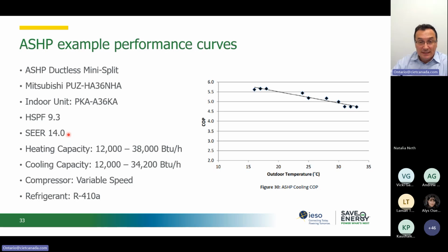So I just mentioned that in the summer we see less delta T. That's reflected in these two parameters. Capacity-wise, we also impact a bit the capacity of the heat exchanger with the temperatures. We can also take advantage in the heating mode of the heat of compression. So the electricity that we put in the compressor is now useful. So for that reason, sometimes you see a little bit higher capacity in heating, as an example here. But what I wanted to point out is the efficiency that we can see here. So when we are looking at cooling, the lower the temperature, the better, because that means we have less work to be done by the compressor. And we can see this here.